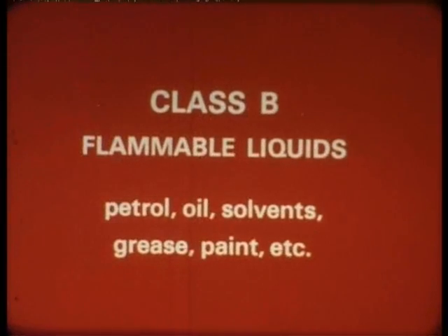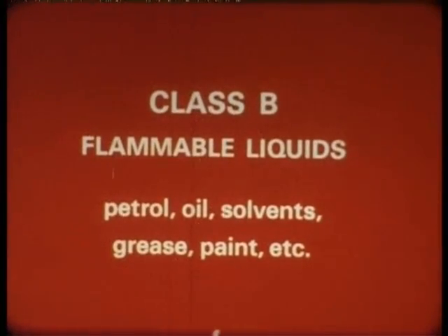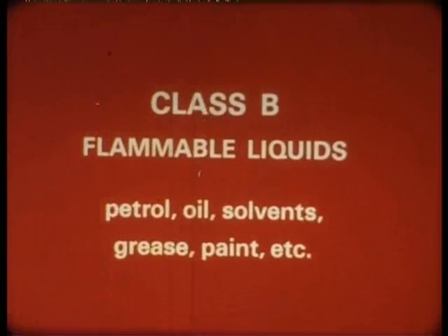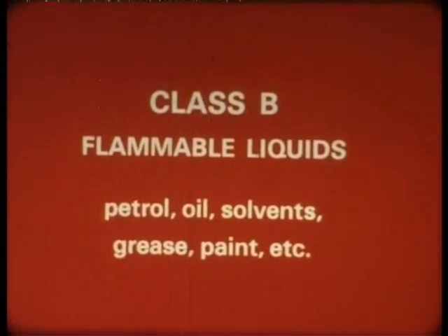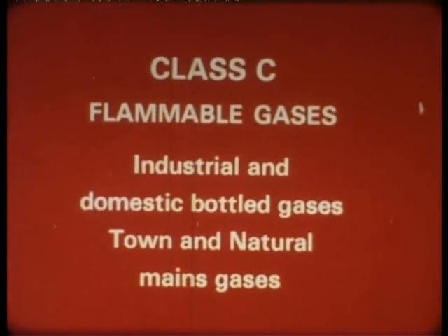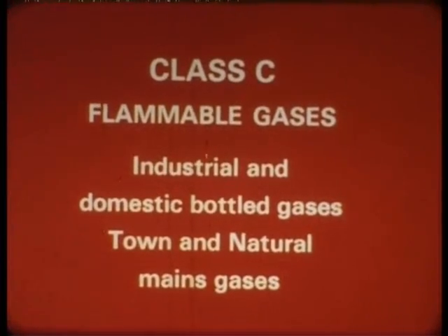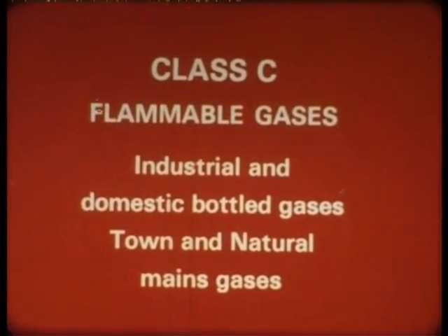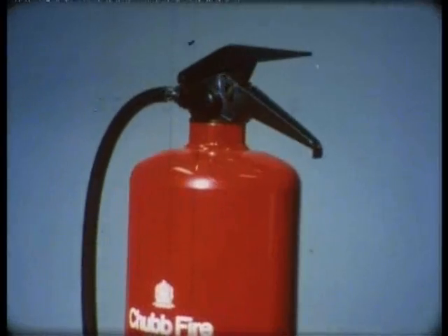Fire falls into three main categories. Class A, involving freely burning materials such as wood, paper, cloth, or soft furnishings. Class B, these involve flammable liquids such as petrol, oil, solvents, grease, paint, etc. Class C, which are those involving flammable gases, including industrial and bottled gases and town and natural gases.